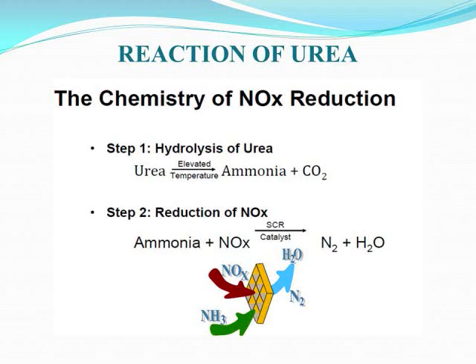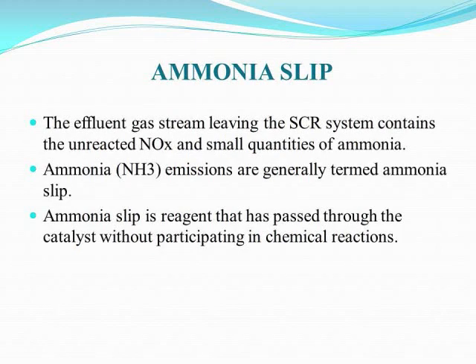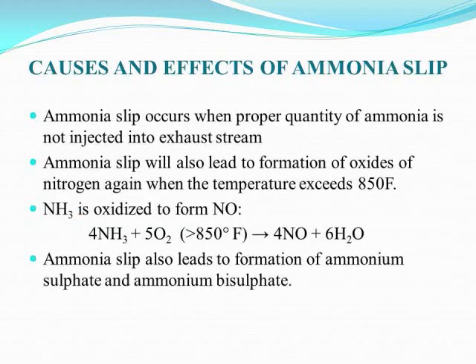The operating principle of SCR: hot exhaust gas from the engine at 450°C enters the SCR system. Urea stored in the urea storage tank is injected into the exhaust. The heat from the hot exhaust reacts with the urea to form ammonia and carbon dioxide. This ammonia then reacts with NOx in the presence of the copper zeolite catalyst to form nitrogen and water, as shown in the chemical reaction on this slide.